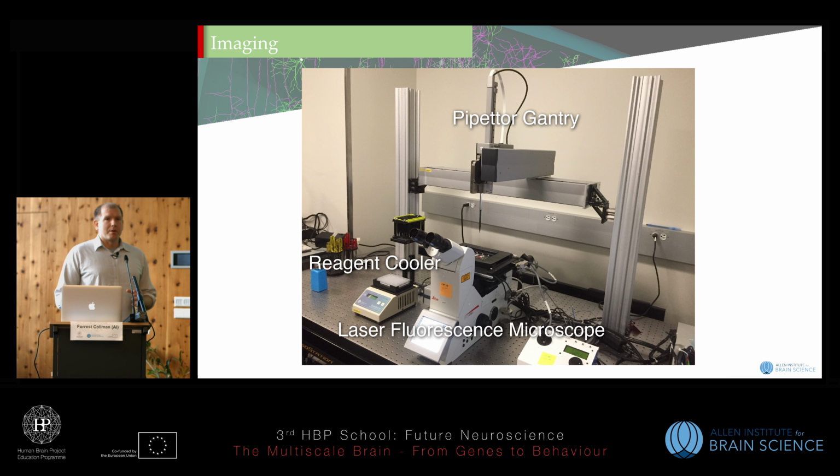Of course, our problem here is not imaging just a single ribbon, but collecting hundreds of ribbons in order to form these large-scale images that we want. One of the limitations on throughput is that if you're doing one ribbon at a time, you need a human there to put the ribbons on and to do the staining. That means your microscope isn't running 24 hours a day, and so you're leaving a factor of 4 or 5 on the table of throughput. So we're trying to develop a system to allow the microscope to run 24 hours a day by integrating a pipetting robot onto the microscope to integrate imaging and staining at the same time.